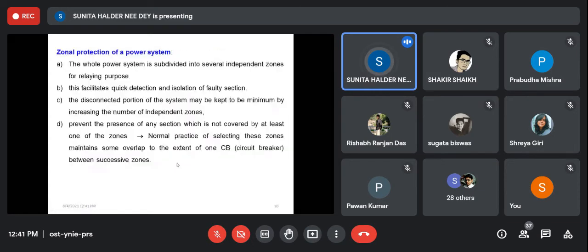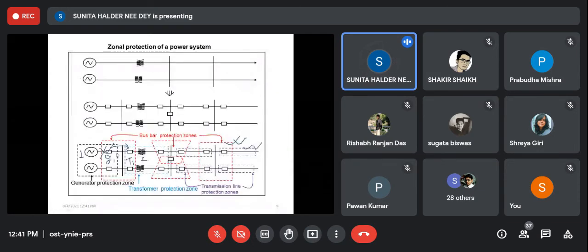So like this, in this protection, say generator 1 has the fault, then G1 may be instructed by two separate relays. So one relay gives instruction, and generator 1's breaker has not operated. Then the second relay gives instruction, then it is operated. Then what are we doing?